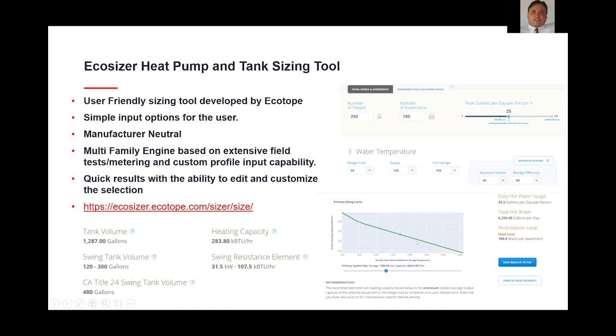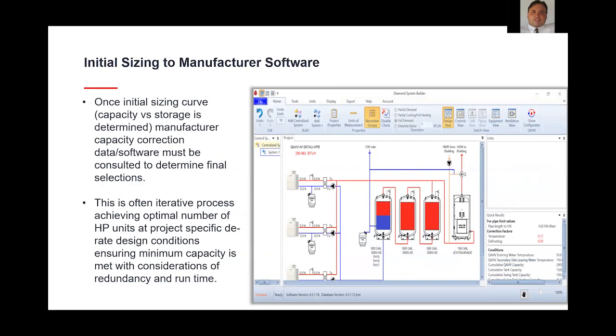And again, once you get this information, once you've gone through this process, looking at your profile and achieving the sizing curve, you can take that data back and start looking at the manufacturer correction data, for what can be achieved from those heat pumps, and see what makes sense in terms of the number of CO2 heat pump water heaters that you need to apply.